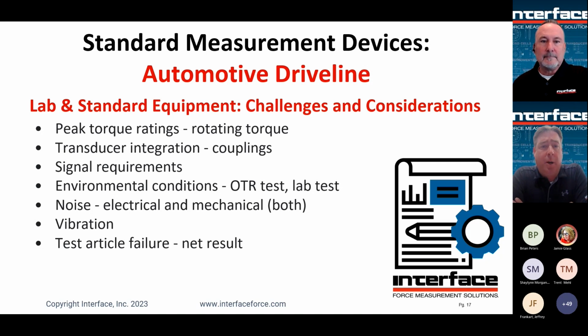Environmental conditions: is it an over-the-road test or a lab test? Those are two very different conditions and environmental ratings. For an over-the-road test, you might imagine testing on a long grade in Colorado in the winter, with salt spray, a pretty rugged environment, versus a lab test where it's very controlled, able to keep the transducer isolated from any environmental effect, with relatively stable temperature. So definitely things to consider there.